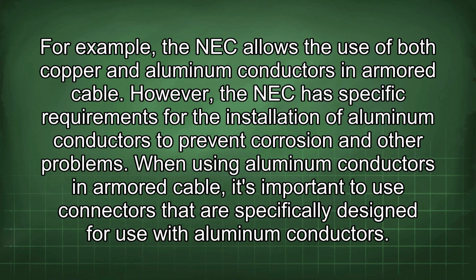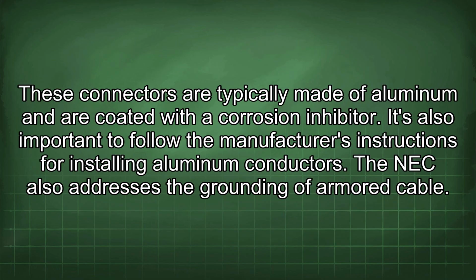When using aluminum conductors in armored cable, it's important to use connectors that are specifically designed for use with aluminum conductors. These connectors are typically made of aluminum and are coated with a corrosion inhibitor. It's also important to follow the manufacturer's instructions for installing aluminum conductors.